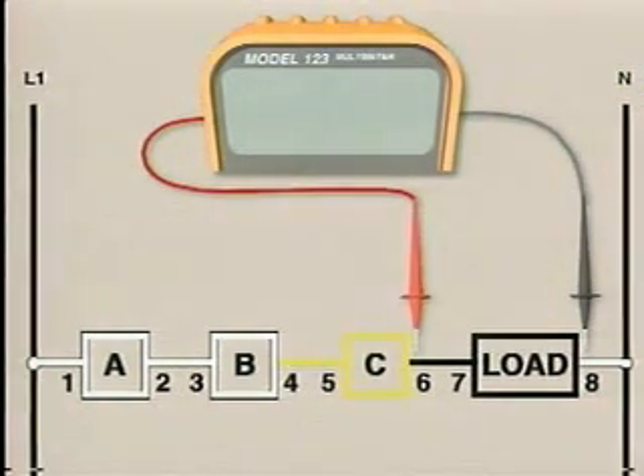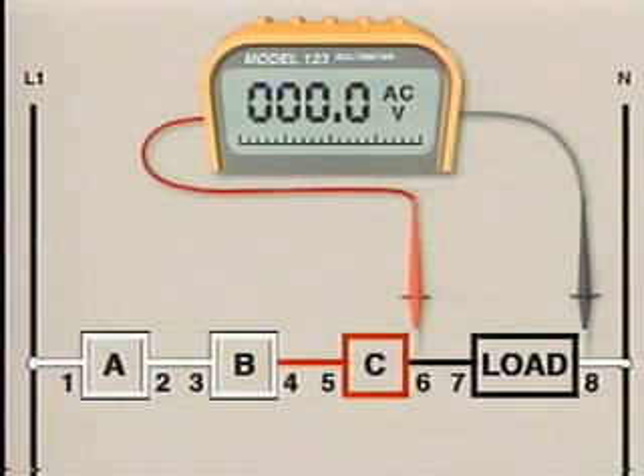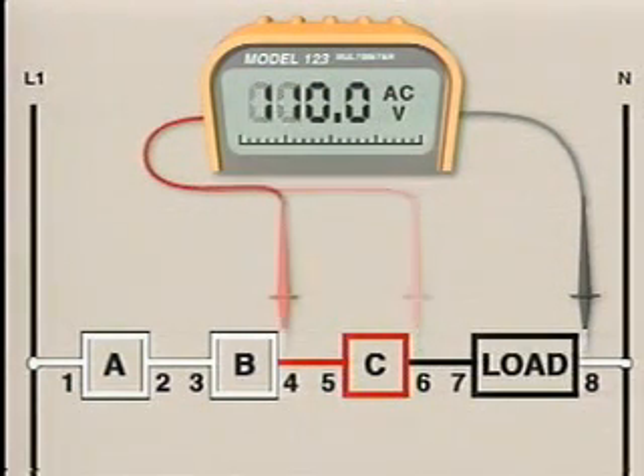This test will check the circuit from test point 4 to test point 6. This time the voltmeter indicates 0 volts. Since we know that there is voltage at test point 4, we can check the voltage at that test point to verify that the voltmeter is still operating properly. The voltmeter is still operational, so the indication of 0 volts at test point 6 means that the circuit's operating voltage, which was present at test point 4, is not reaching test point 6.